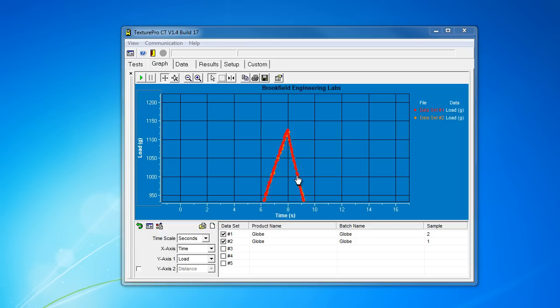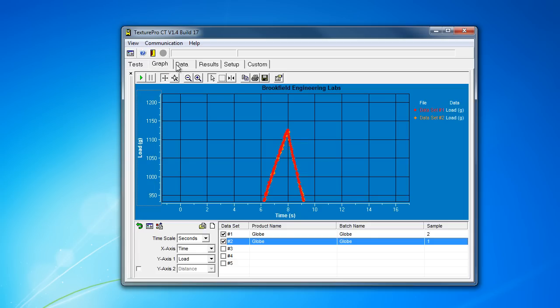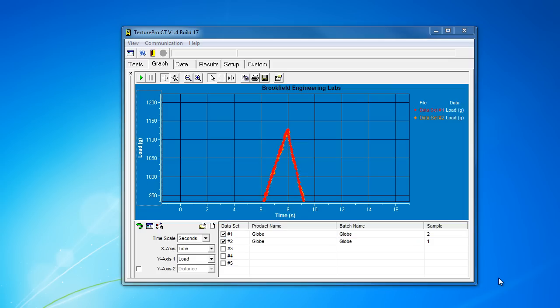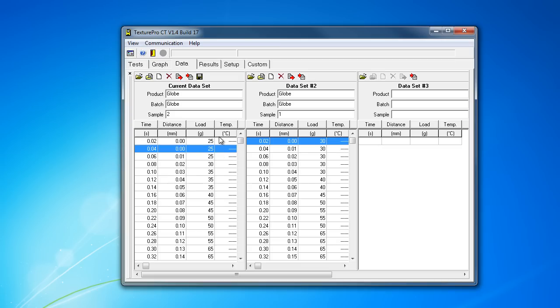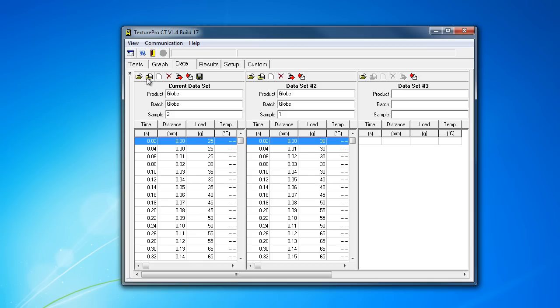You see here I've got these two graphs, but in order to do any sort of calculations on them, my best bet is actually to export this data individually and then run the comparisons in software such as Excel. The actual texture pro software itself has barely any indication that comparisons are even doable. Not only does the software lack any sense of being able to build preset calculations or the ability to create custom macros as seen by more advanced texture analyzers, but even its ability to export the data is really weak. As I mentioned before, your ability to export data can only be done one by one. You can print out a PDF with individual numbers for an individual test, or you can one by one actually go out and export each replicate as its own Excel file.